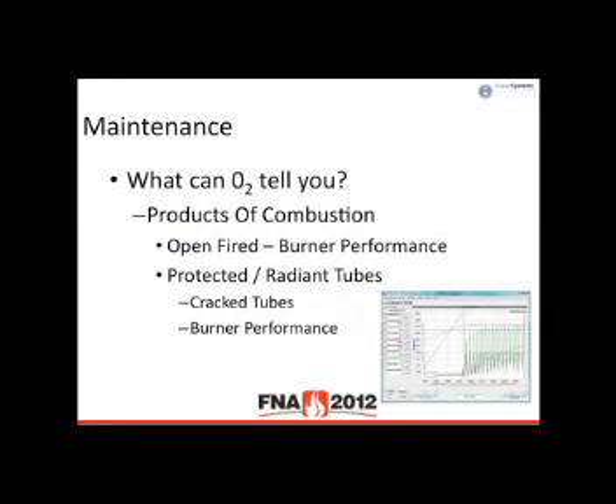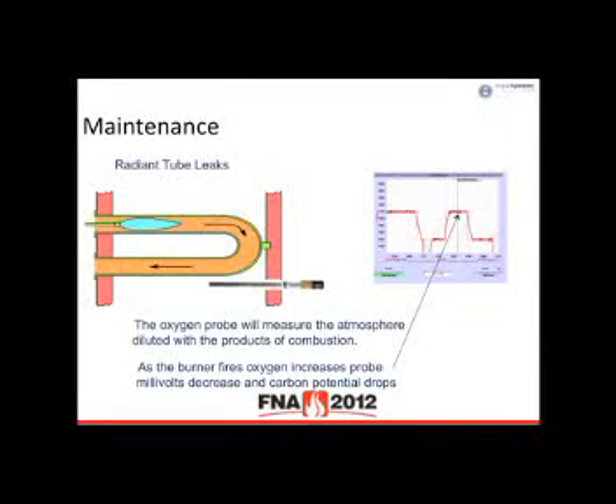A couple other points when we look at some of the troubleshooting topics or maintenance. Oxygen. When we look at protective atmospheres, there's a couple pieces I want to look at here. When you look at radiant tubes where you have a crack, you can look at the millivolts of a probe, and you're going to see that you have a tube leak or a crack in the tube because the millivolts are going to drop. When millivolts drop, you go to high fire. So on that tube you go to high fire, millivolts start to drop, and all of a sudden I'm throwing a bunch of gas in there. So you have an uncontrollable process. But that's just an example of additional information that maintenance can utilize to troubleshoot a problem.